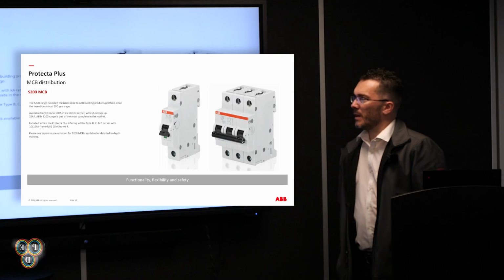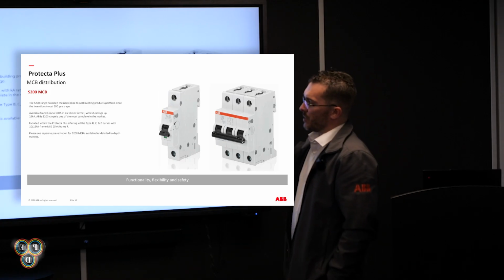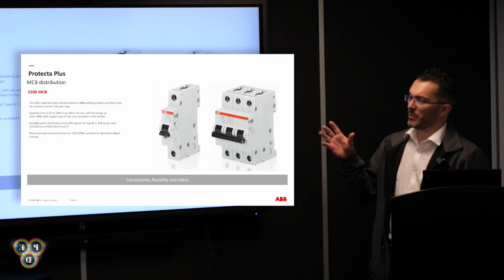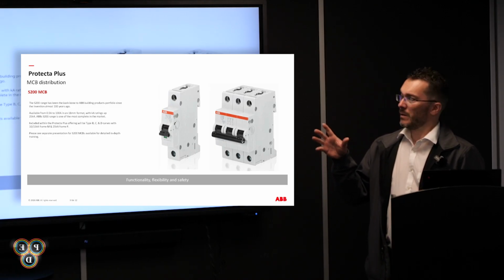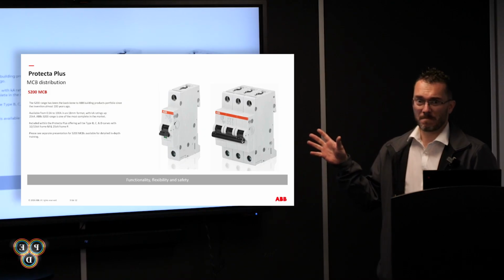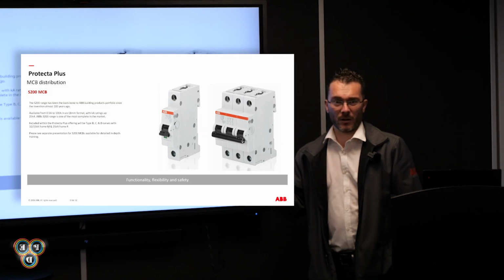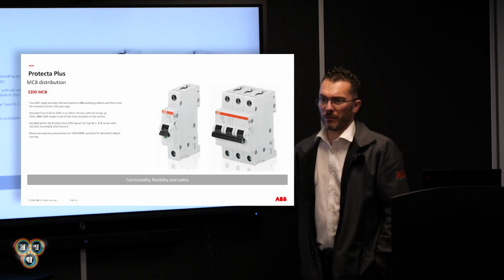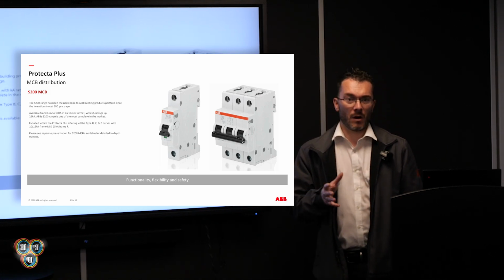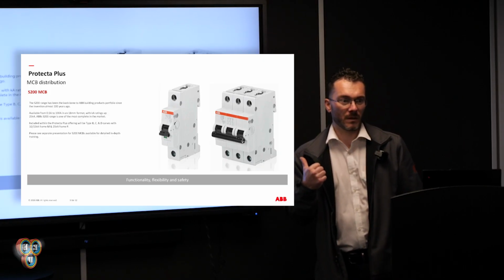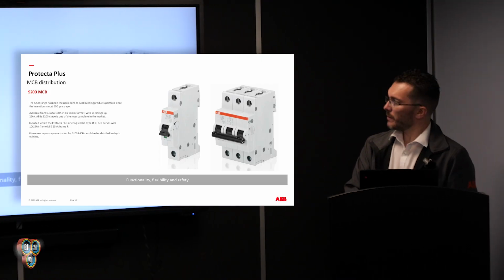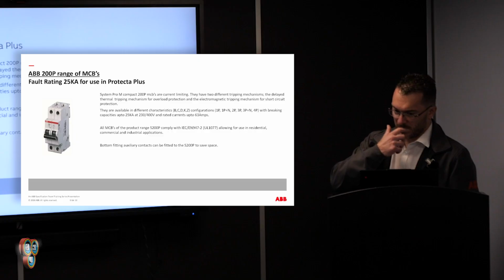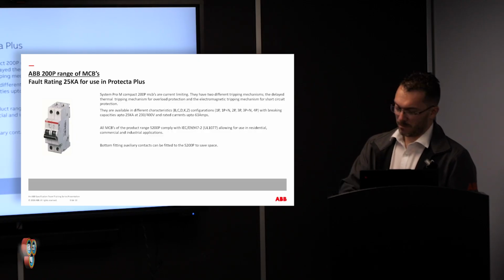In terms of the MCBs that fit within these, our range is the S200 range. They go up to 100 amp, pretty much standard 10-15 kA. We do, however, have an S300 range. It used to be the S200P range. We've now got an S300 range, which is up to 25 kA. So if you've got a high predicted fault current, we do have a 25 kA option in an MCB frame size that will fit within the distribution boards. This is an old slide, so it covers the S200 range, but it coincides with the re-release of the S300s.